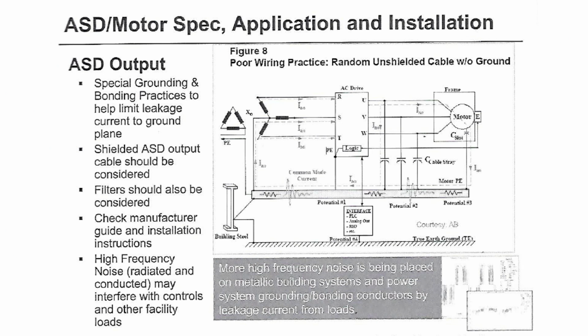So, more specs and application for VFDs. Shielded cable. Have any of you seen a VFD cable? Right over here. Have any of you seen VFD cable? You probably never will because it's very costly. I think I saw one on a transformer. Anyway, it looks like that. It's got a separate conductor, a separate ground wire for each conductor, and each conductor's got a shield around it. That shield is to capture that high frequency. The ground wire is to drain that so that it don't get to the motor. But the chances of you ever putting it in, slim to none. Because it's very costly. So, what's my alternative to that?